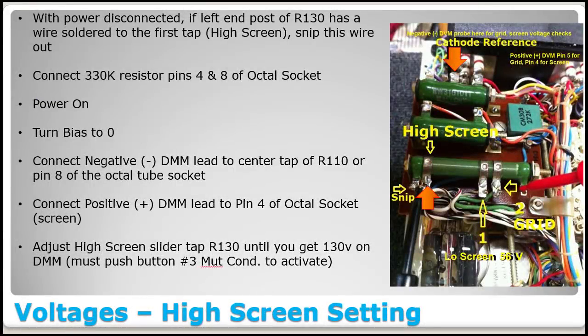Alright, let's move on to setting the high voltage screen setting. And what you want to do is, with the power disconnected, check out R130 right here. Down here on the end, see where my test lead is connected, there is a jumper between this very end of the potentiometer and this first movable point right here. You're going to want to snip that little jumper if it's still in there.